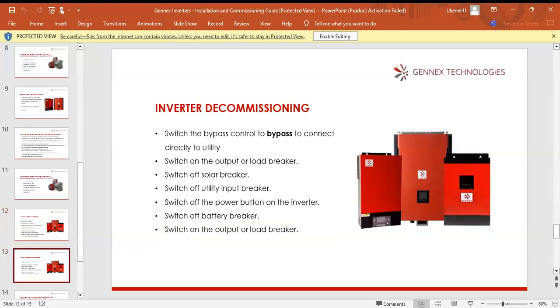Inverter decommissioning. When you want to decommission, that is, to shut down the system, there is also a sequence you follow. Switch the bypass control to bypass, because when you want to remove the inverter, you want the owner to be able to operate on NEPA or generator. You may not be removing the inverter; probably you want to carry out some troubleshooting and you don't want this to affect the client. You do that so that while you are troubleshooting, the client can be on direct utility supply. Then switch off the output or load breaker. Then you switch off the solar breaker, and you switch off the utility.